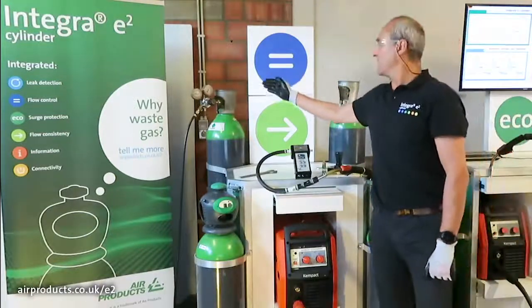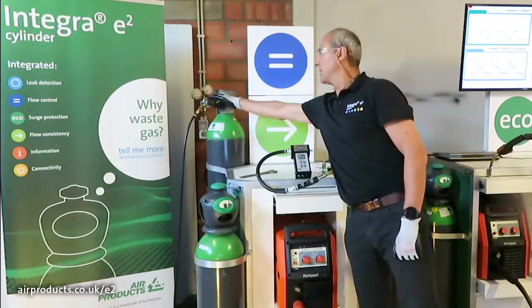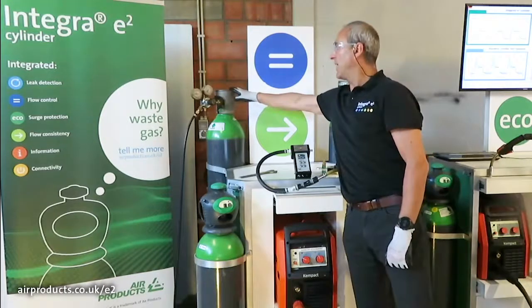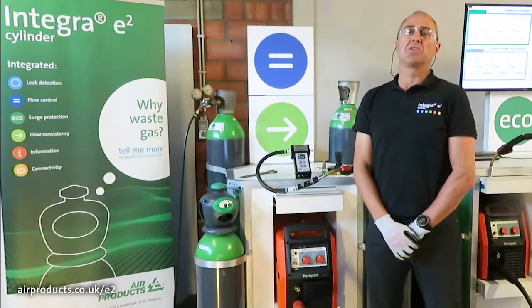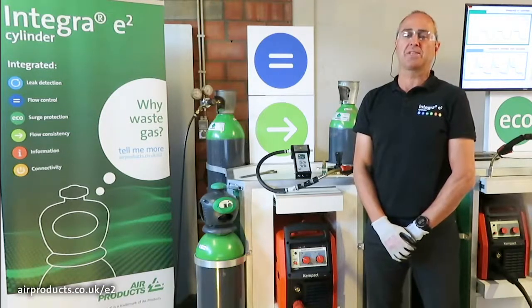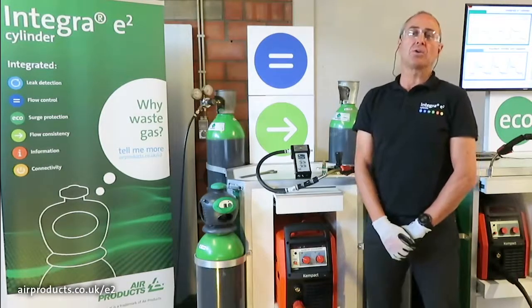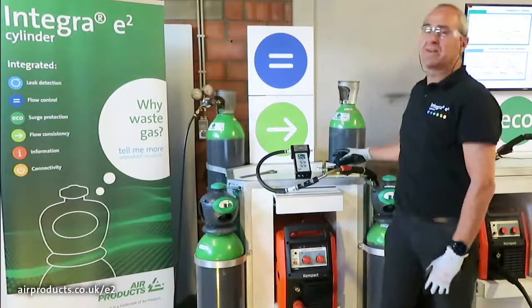If we look at the standard cylinder setup, the flow rates are controlled by a standard regulator connected to the outlet valve of the cylinder. This standard regulator, as already explained in the flow control video, can easily be set to give an excessive flow rate and therefore lead to considerable excessive gas waste. Often this type of equipment is poorly maintained, or when buying poorly manufactured and inexpensive regulators, the flow characteristics of this regulator can be very unstable. How can this happen?